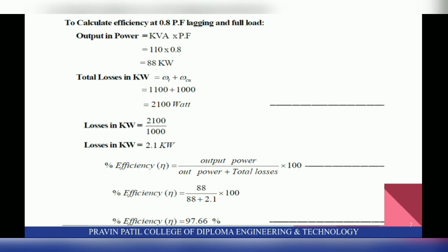Next, calculate efficiency at 0.8 power factor lagging and full load. Output power = kVA × power factor = 110 × 0.8 = 88 kW. Total losses = Wi + Wcu = 1100 + 1000 = 2100 Watt = 2.1 kW. Efficiency = output power / (output power + total losses) × 100 = 88 / (88 + 2.1) × 100 = 97.66%.